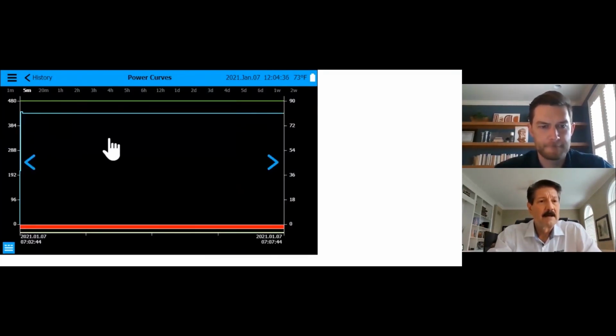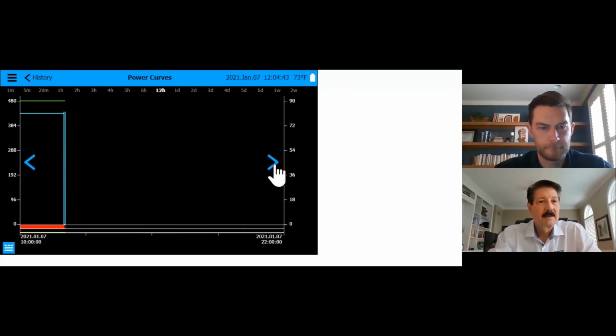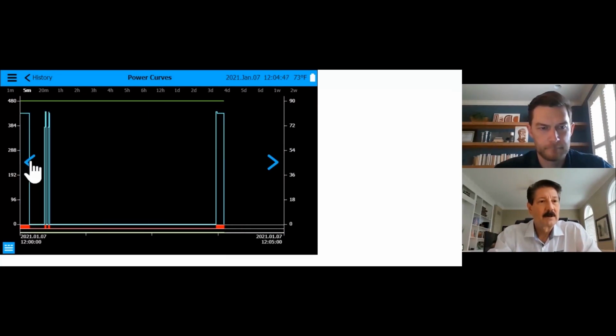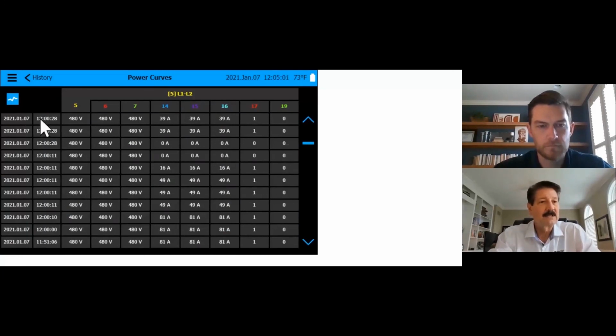Power curve, same way. In this particular case, I'm going to bump this up for viewing real quick, and I'm going to drill it down a little bit more. There we go. So what we have is motor running here on the bottom horizontal and increases in current. That's what we're seeing here. Motor starts. If I were to convert this to a spreadsheet, again, what we see is date stamp. Here's your voltage, A, B, C. Current, A, B, C. And we have current because under 17, the pump's been running. 19 will show me whether I'm on alternate power or not. And this is really good data because if there's a problem where the motor is drawing excessive current on one of 3 phases, it will highlight it here.